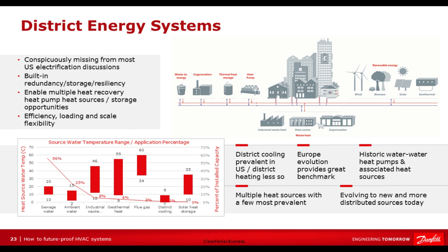If you're reconnecting supply and demand based on the integration of renewables, a district energy system incorporating thermal energy storage is a fantastic way to do that, because of both the thermal flywheel effect of the district energy system itself, as well as the options it creates for recovering heat off different sources in the system, moving it to where it's needed and away from where it's not, and then turning down those generation sources as needed based on demand signals or demand response signals from the utility.